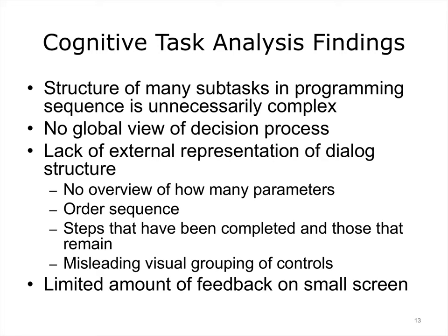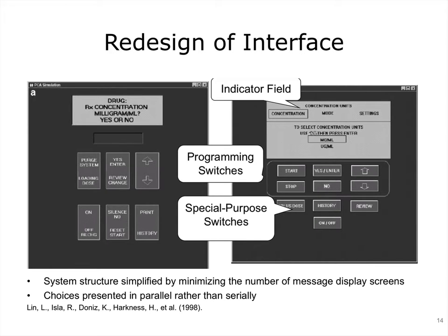On the basis of the cognitive task analysis, Lin et al. found the existing PCA interface to be problematic in several ways. For example, the structure of many subtasks in the programming sequence was unnecessarily complex, there was no overview of the entire task, and there was a lack of external representations to guide the user. A nurse would not know that he or she was on a third of five screens and was halfway through the task. The grouping of controls was very confusing with some buttons serving two functions, and the screen was rather small, limiting the kind of feedback that was possible. They also redesigned the interface according to sound human factors principles.